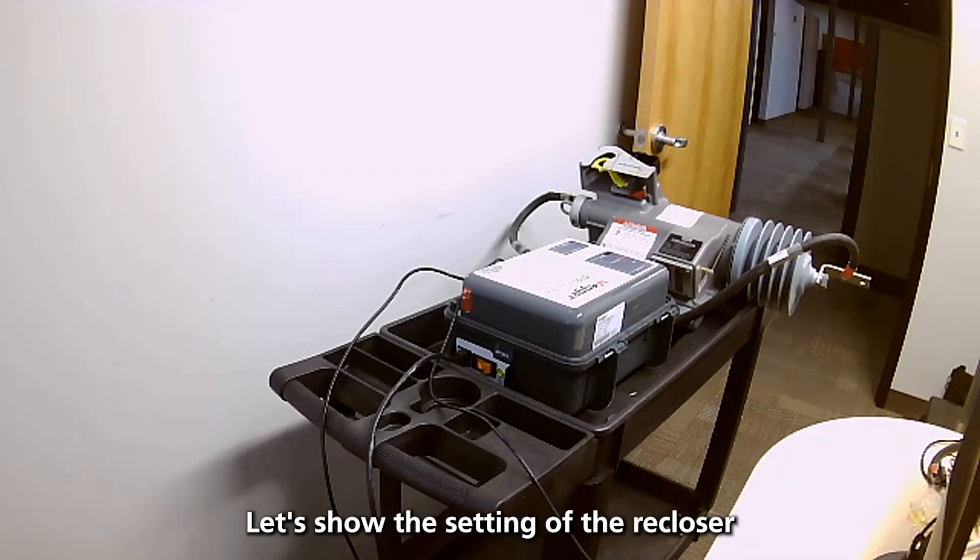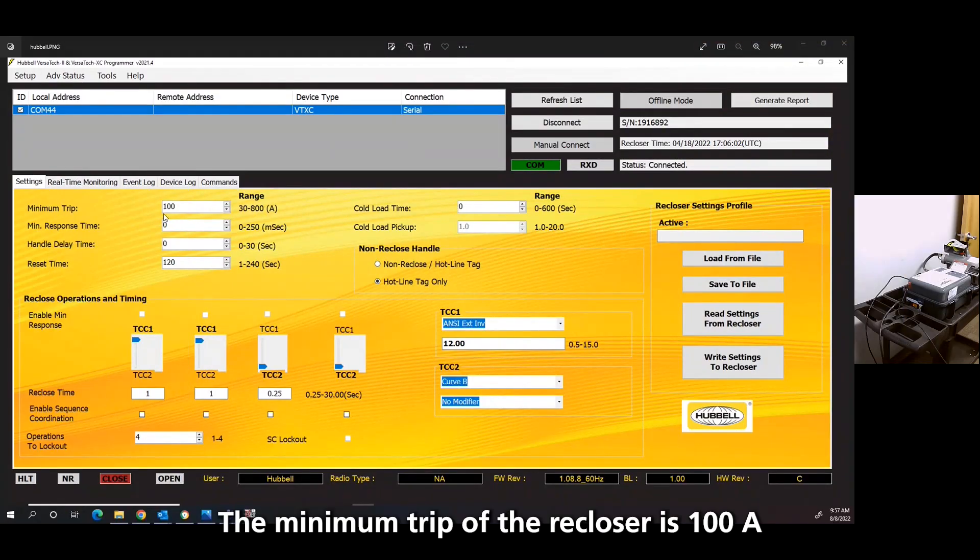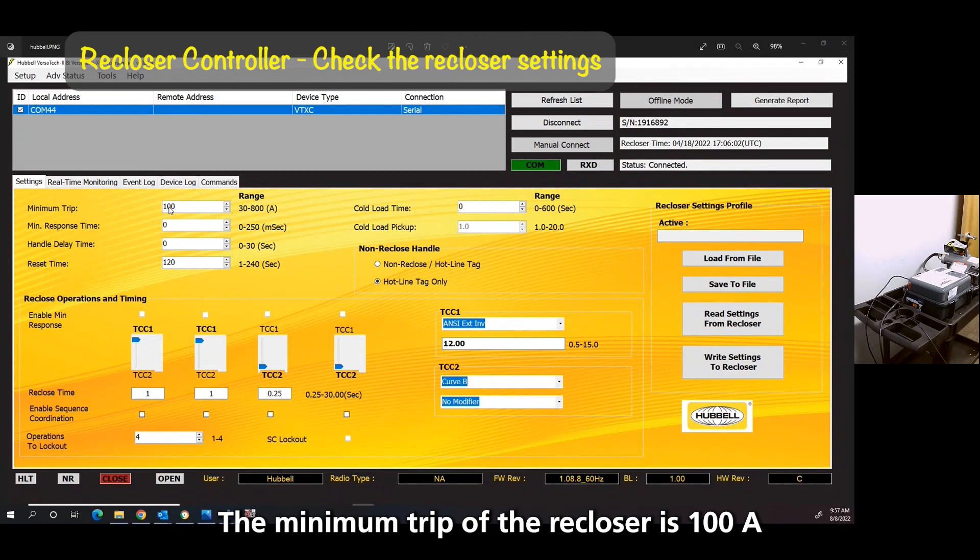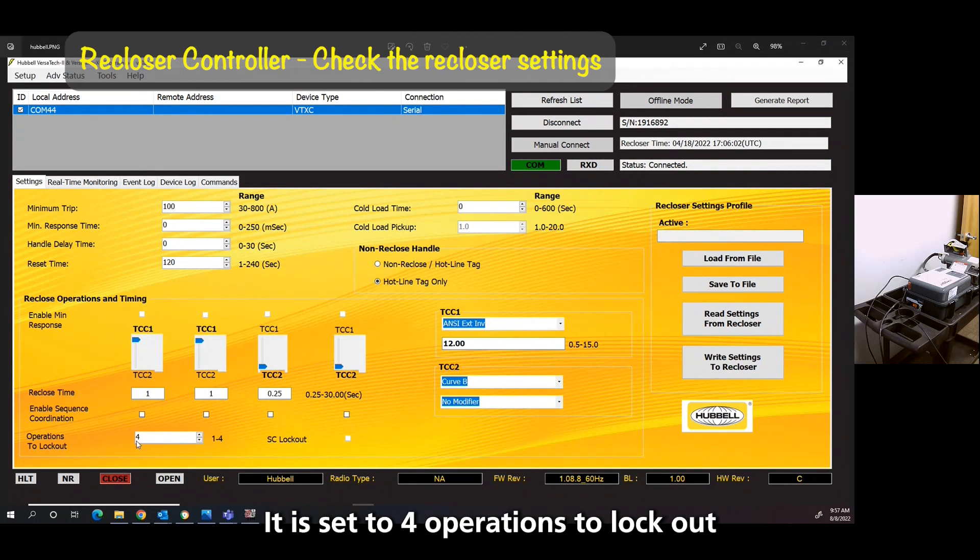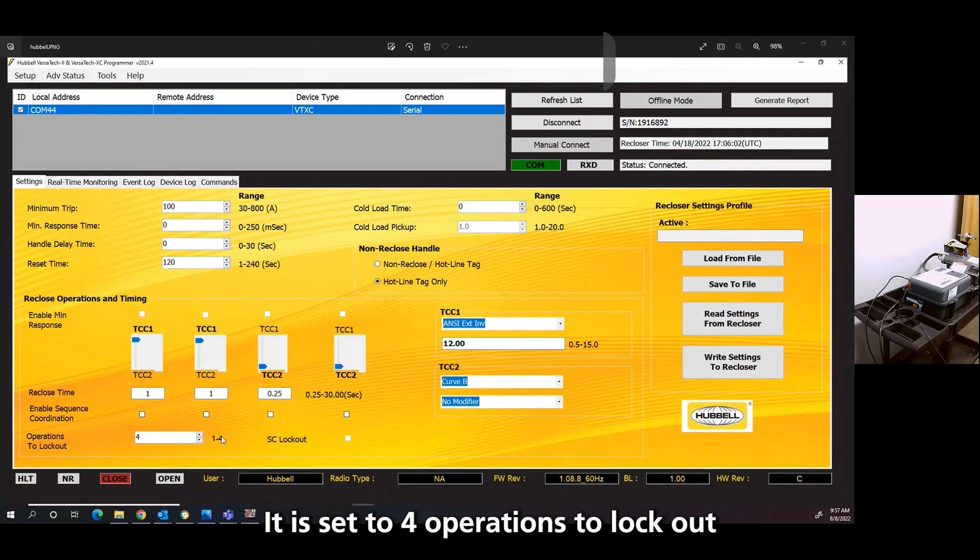Let's show the settings of the recloser. The minimum trip of the recloser is 100 amps. You can see it's set four operations to lockout.